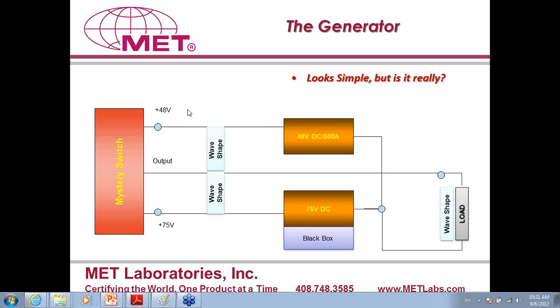So using an extremely high-speed electronic switch with current handling capability of more than 400 amps, we hooked up two power supplies. One power supply can provide up to 600 amps at 48 volt DC. The other power supply can provide 75 volt DC with an adjustable output, which could take us anywhere from 0 all the way up to 300 volt DC. We hooked up that power supply to the other input of the single pole double throw switch. We combined the returns of those two power supplies. The output of the generator basically is the output of the single pole double throw switch, which will be hooked up to the load.